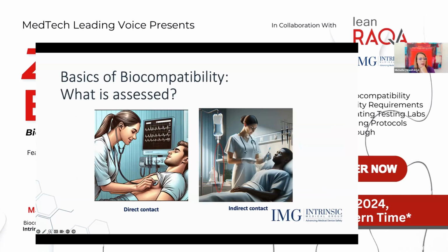One of the questions I got beforehand is: what happens about those products? Especially in some of the 60601 series, they call out some biocompatibility requirements, and they say things like parts that are intended for direct or indirect contact with biological tissues, like you were talking about. But what about parts that have no contact or only transient contact, like a lead inside an electrode that doesn't actually touch the patient? What about those parts?